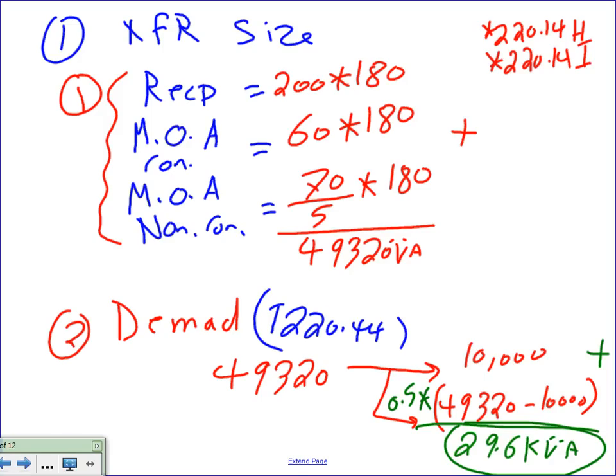Any question? That's what they call it, the demand. So this number is 49 kVA. A lot of people size based on this: if you convert this one, that would be 49.3 kVA. Look at this.